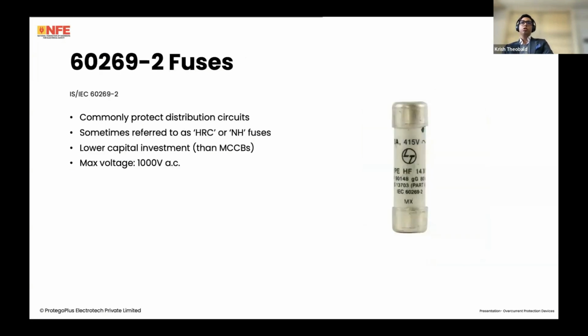Then we've got the humble 60269 Part 2 fuse. Once again, there is a corresponding IS standard. It's IS IEC 60269 Part 2. These commonly protect distribution circuits again, so cables that go to sub-distribution boards from the main distribution board. These are often referred to as HRC, high rupturing capacity, or NH. It's a German term that also means high rupturing capacity. These require a lower one-time capital investment as compared to MCCBs because purchasing a single fuse and a switch fuse disconnector is not as expensive as say an MCCB. However, if it blows, if it fuses, you have to replace it. That's something to keep in mind.